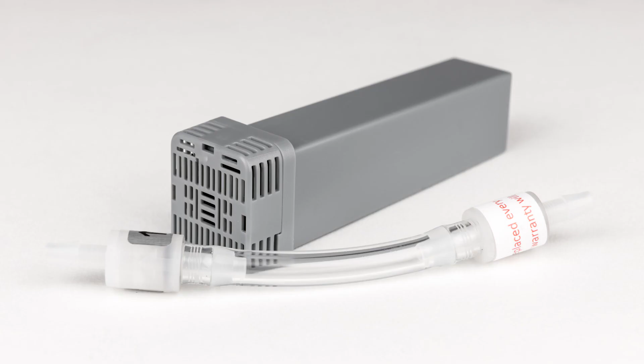There are a few things to do when looking after the SoClean. Keep the SoClean clean and dust-free by wiping it down with a damp cloth when necessary. The check valve assembly, located along the length of the black hose, prevents water from the humidifier reservoir from backing up into the SoClean. If you can see water in the clear section of the tubing, the check valve assembly should be changed. It is recommended to replace the check valve assembly every 6 months. The display screen will flash reminders to make the replacement when the time has arrived. The filter cartridge is also recommended to be replaced at the same time.